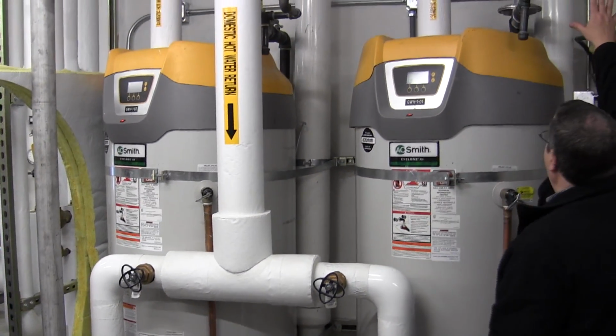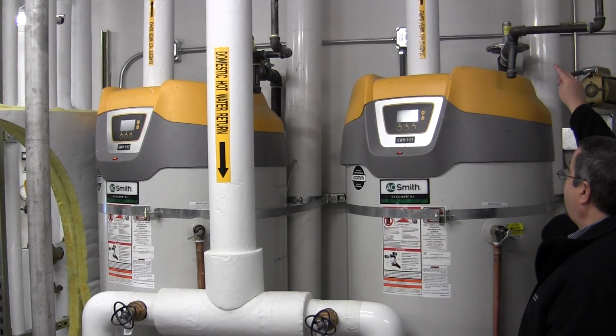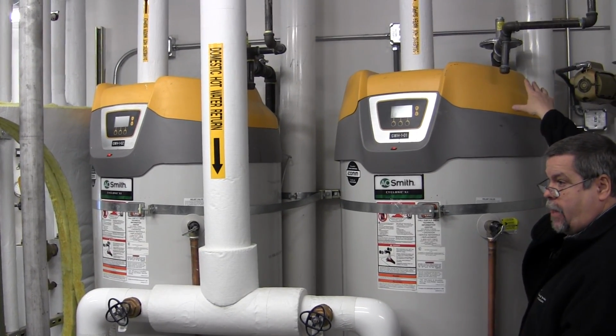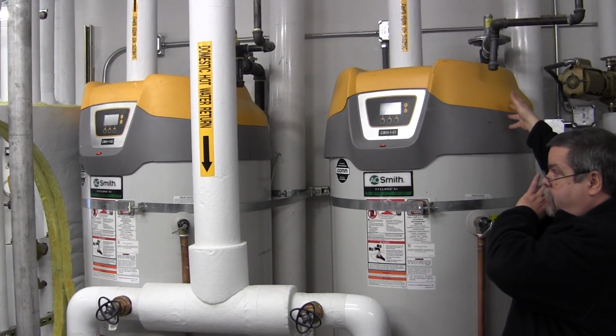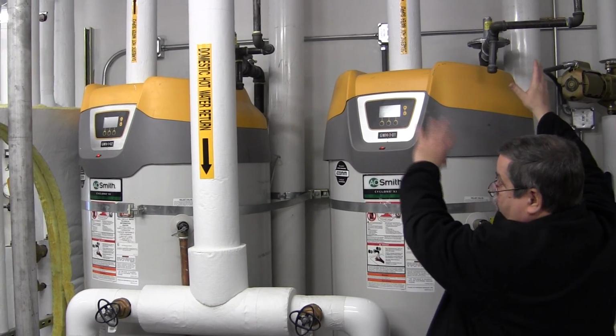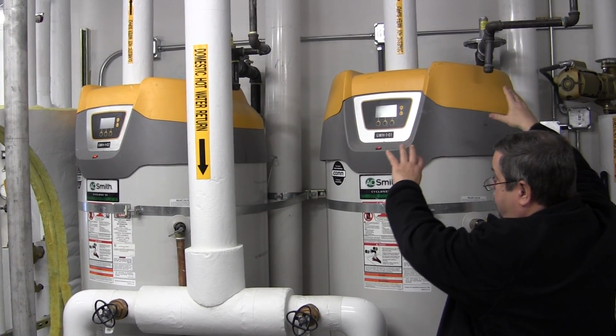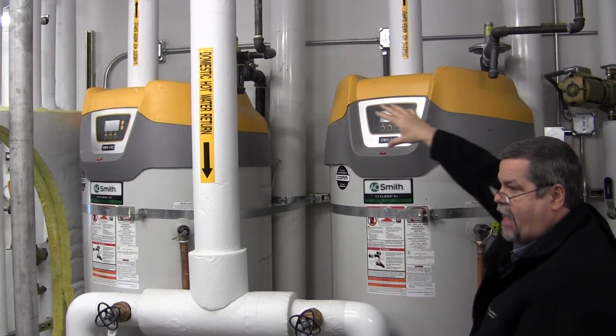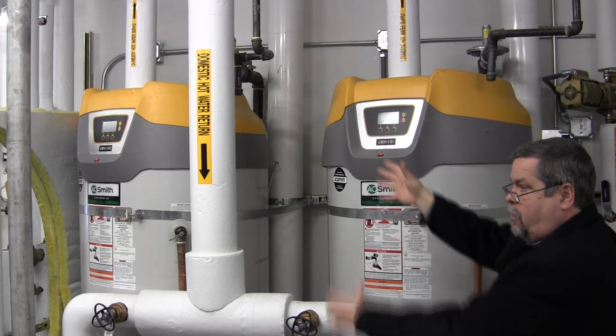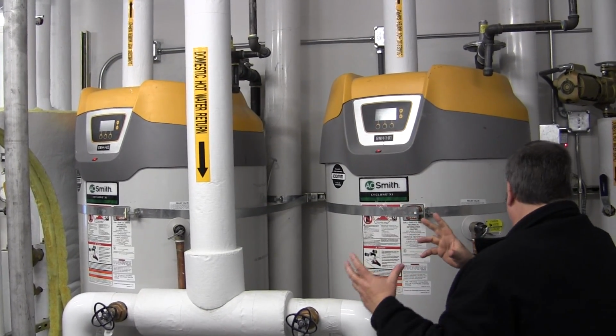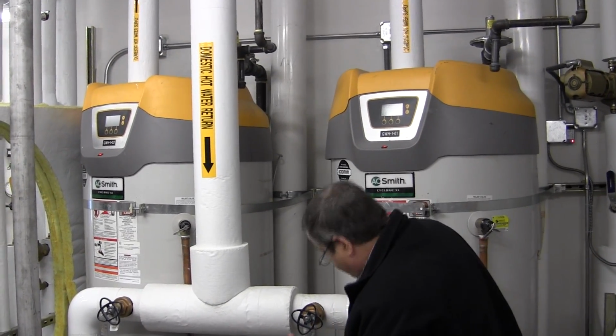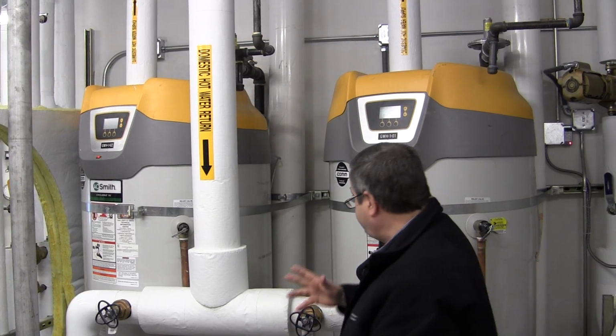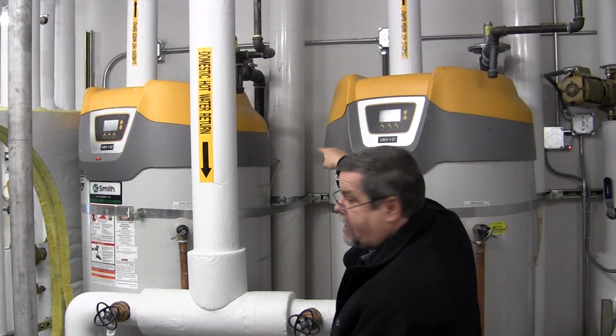You've got your incoming gas here, and you've got an aftermarket regulator that's not part of the A.O. Smith system, but we want each of these to have their own regulator, which they do. And then the gas goes into the gas train, which is up on top of the unit. There's a blower up there. There's 3 pressure switches. One of the key maintenance points is on this exhaust vent.